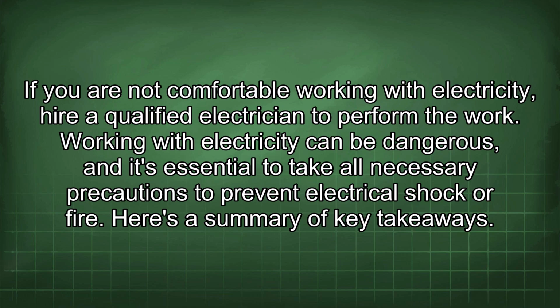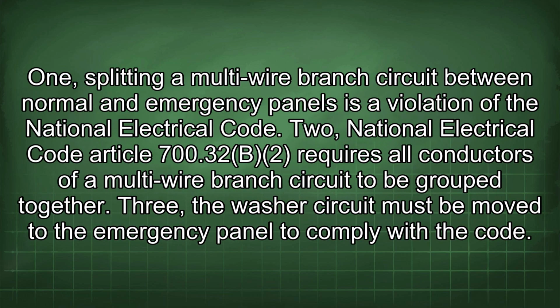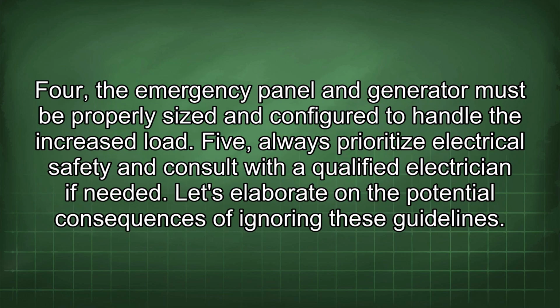Here's a summary of key takeaways. 1. Splitting a multi-wire branch circuit between normal and emergency panels is a violation of the National Electrical Code. 2. National Electrical Code Article 700.32(B)(2) requires all conductors of a multi-wire branch circuit to be grouped together. 3. The washer circuit must be moved to the emergency panel to comply with the code. 4. The emergency panel and generator must be properly sized and configured to handle the increased load. 5. Always prioritize electrical safety and consult with a qualified electrician if needed.